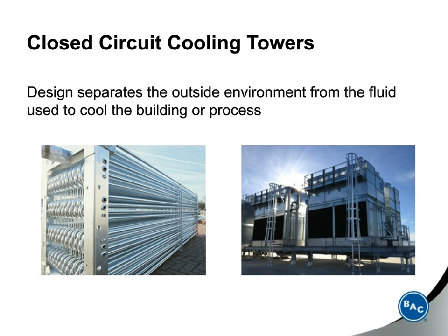Now, a closed-circuit cooling tower actually isolates the condenser loop through a serpentine heat exchange coil. This coil is shown on your screen to the left. This is placed inside of the closed-circuit cooling tower, and the tower recirculates water over the coil, and that's where the evaporative cooling occurs. Now, the process fluid inside the coil is transferring heat through sensible heat rejection, so that's not evaporating, but the evaporation that's occurring on the coil is what really enhances your heat transfer.